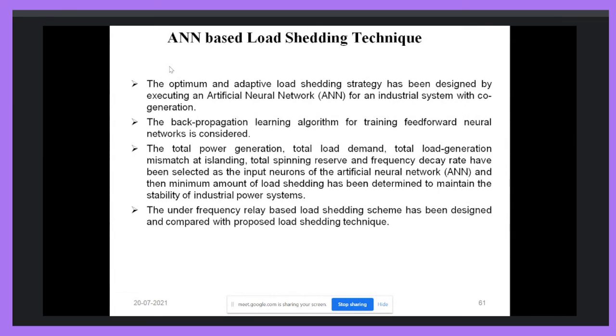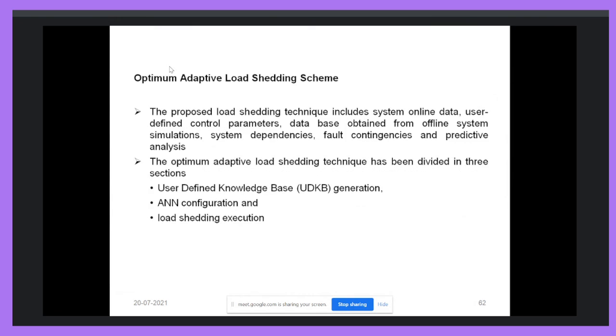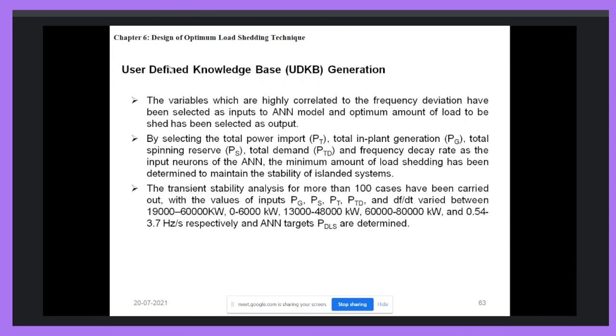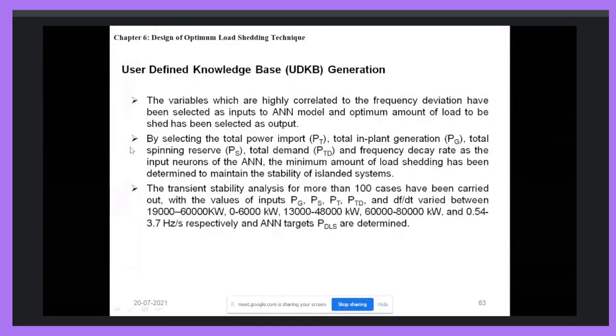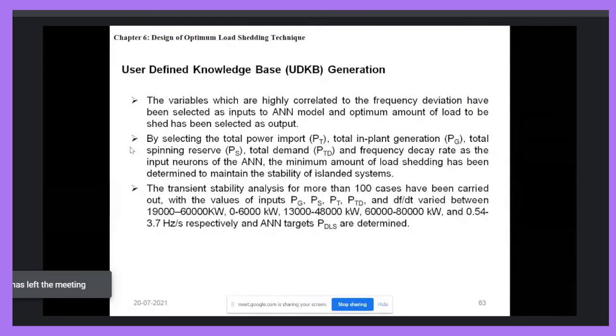So the under frequency relay based load shedding scheme has been designed and compared with the ANN based load shedding scheme. To design the artificial neural network, as we discussed, we need a user defined knowledge base, meaning the data bank for training and testing purposes of the artificial neural network. We have to create that. Then we have to configure the ANN. Configuring the ANN means we have to decide what the input to the artificial neural network should be and what the output of the neural network will be. So by selecting total power import PT, total plant generation PG, total spinning reserve, total demand and frequency decay as input to the ANN, the minimum amount of load shedding is determined.